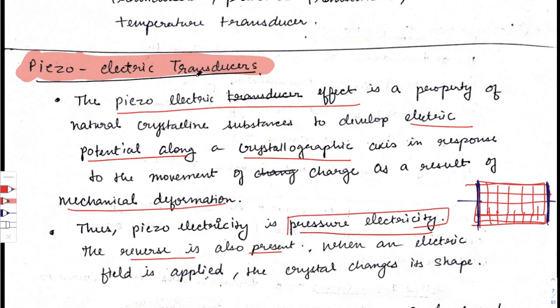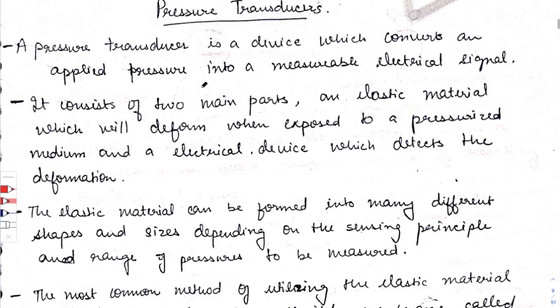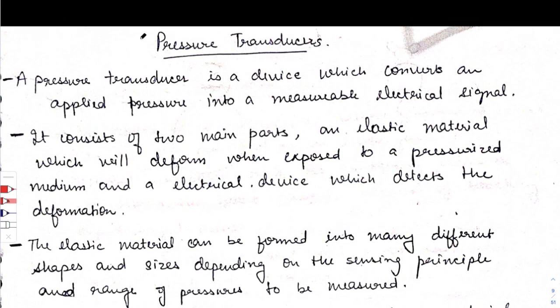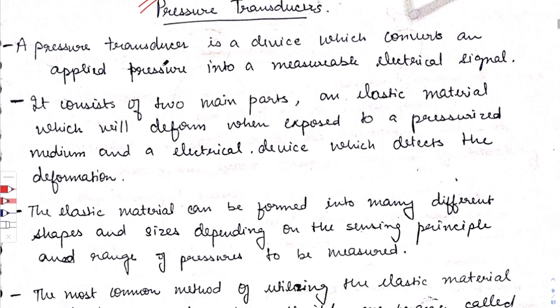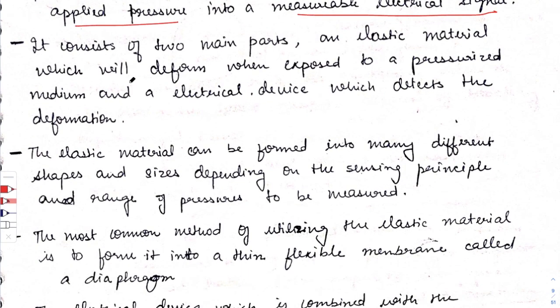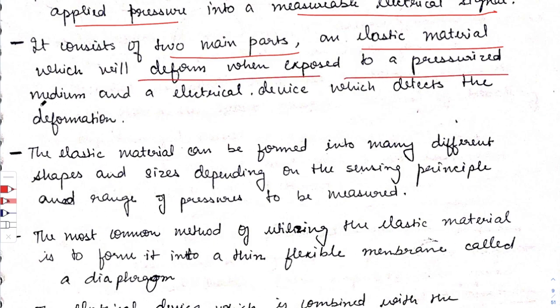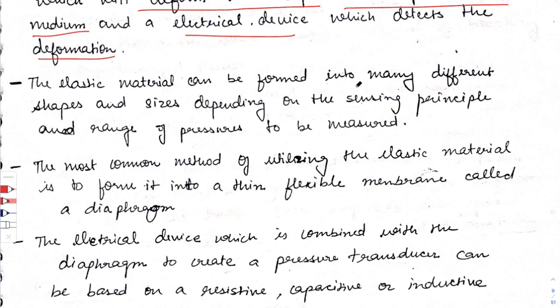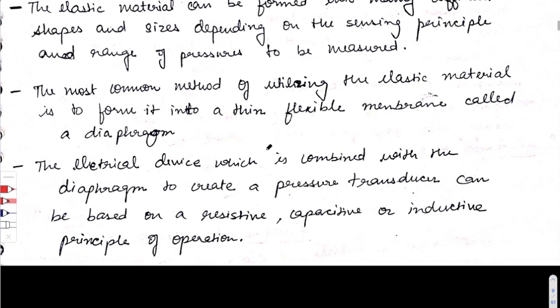Coming on to pressure transducers: a pressure transducer is a device which converts an applied pressure into a measurable electrical signal. It consists of two main parts — an elastic material which deforms when exposed to a pressurized medium, and an electrical device which detects the deformation. The elastic material can be formed into many different shapes and sizes depending on the sensing principle and range of pressures to be measured.